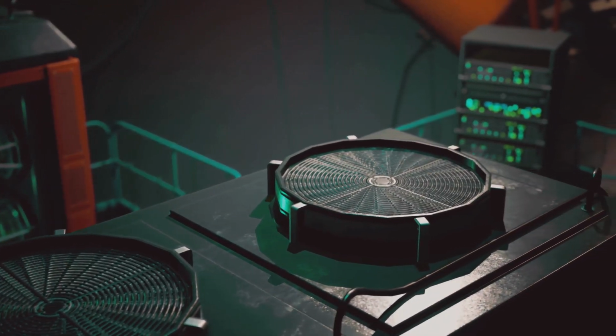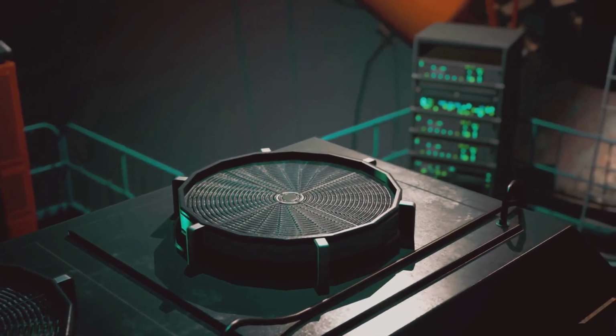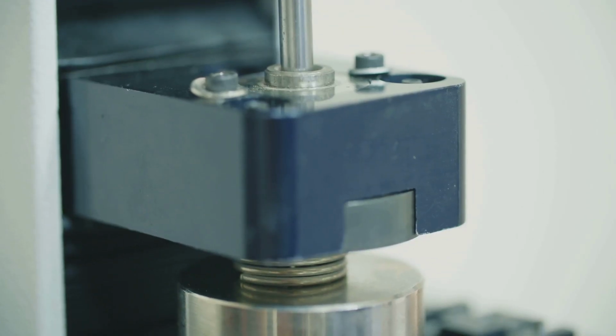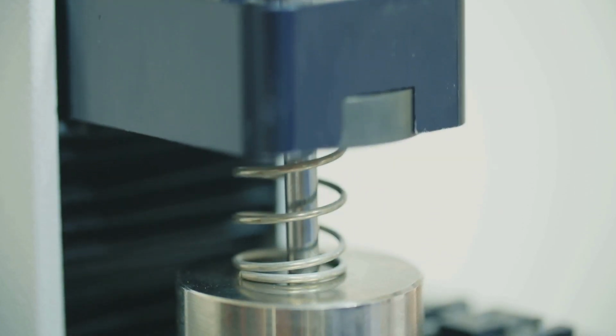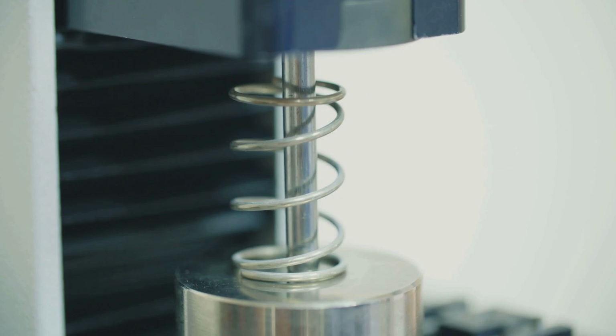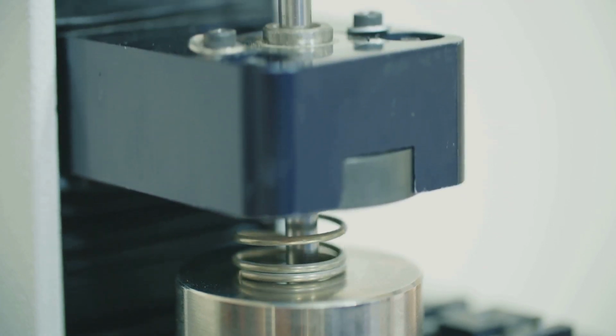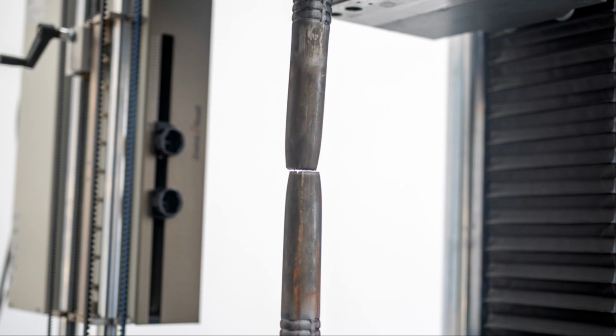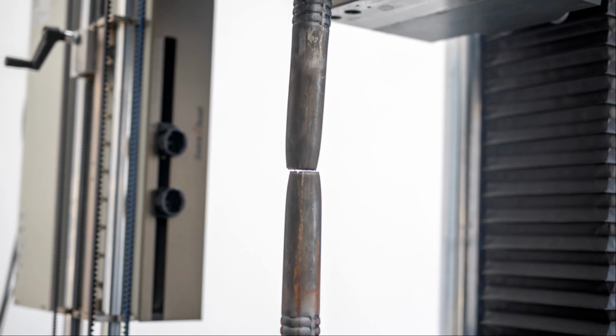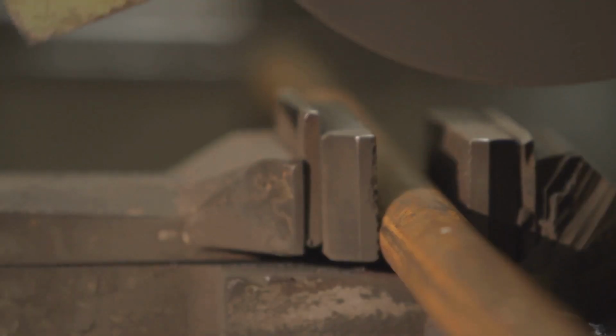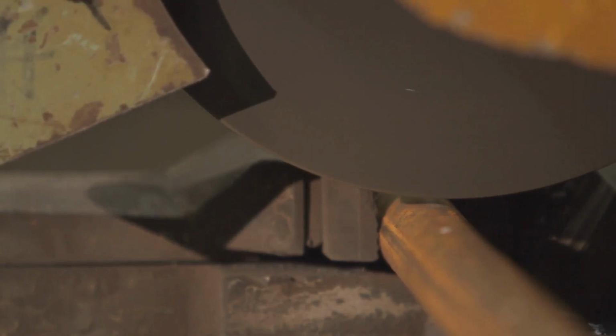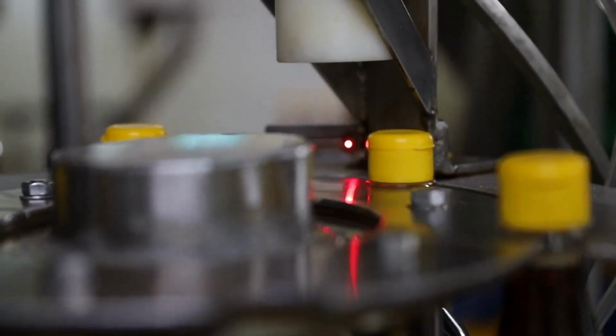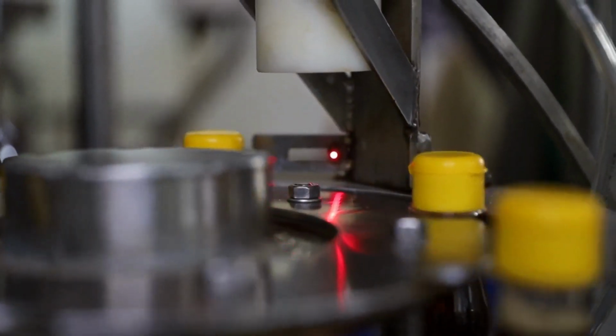The right choice of extensometer for a test is dependent on several factors. The type of material and any test standard requirements will help focus your search, especially when considering different stiffness classes like elastomers versus metals, expected elongation, and whether you need to measure before or at yield. Other considerations include the clamping force required by a contact extensometer, specimen thickness, or the requirement for non-contact measurements.